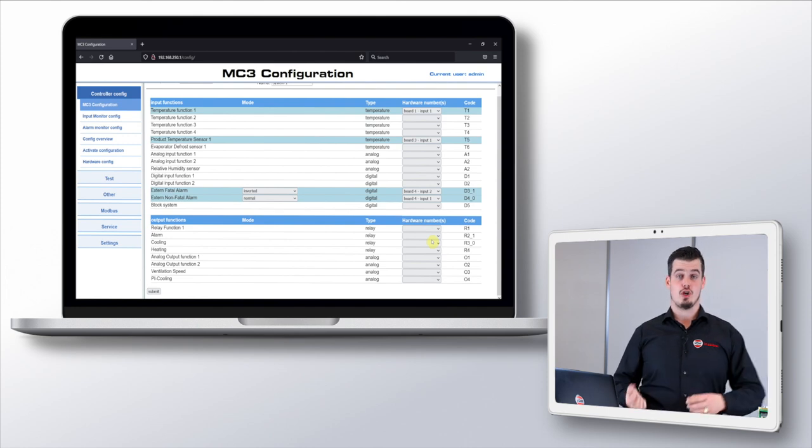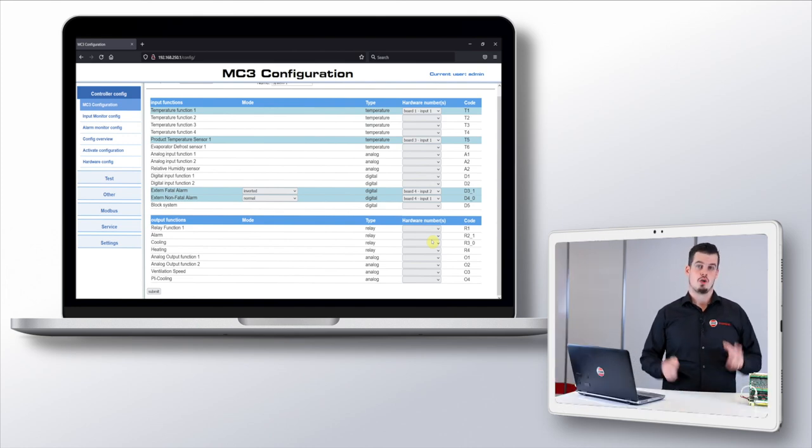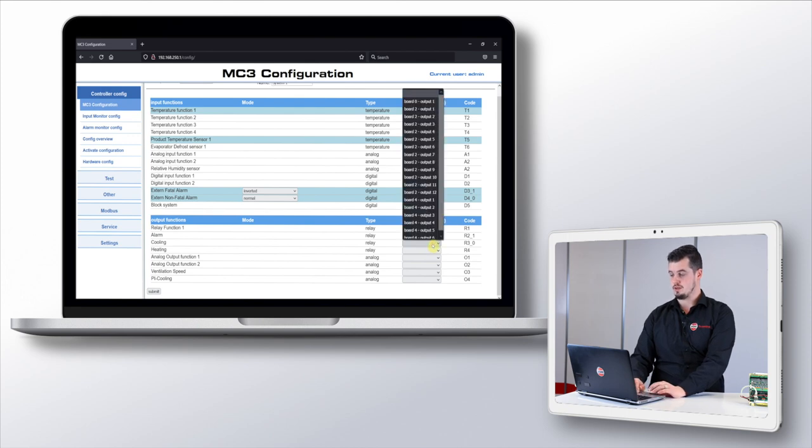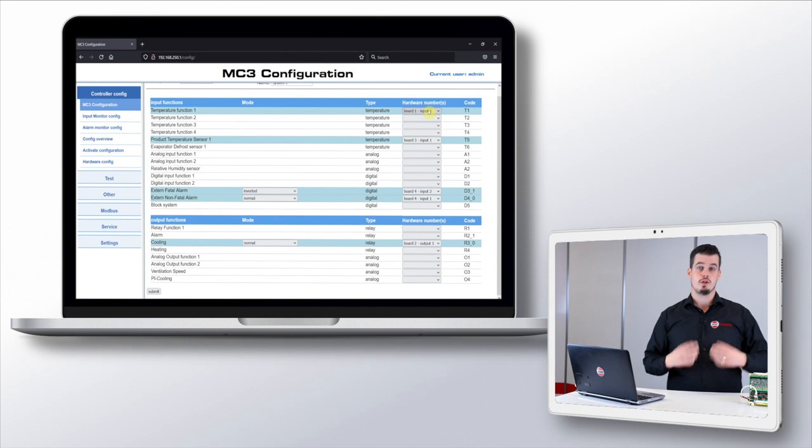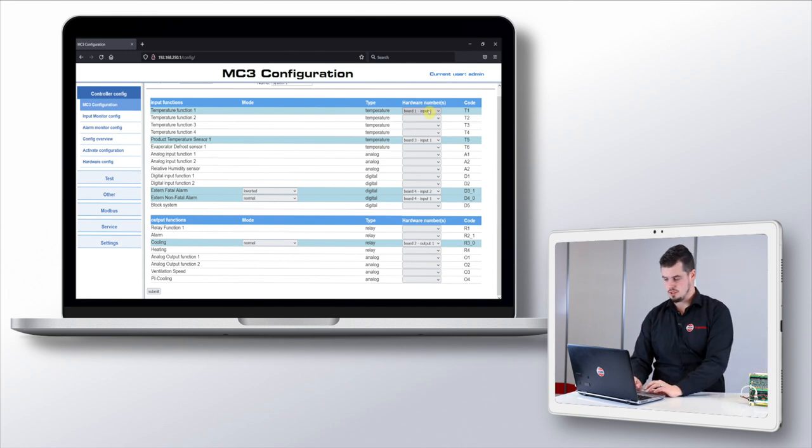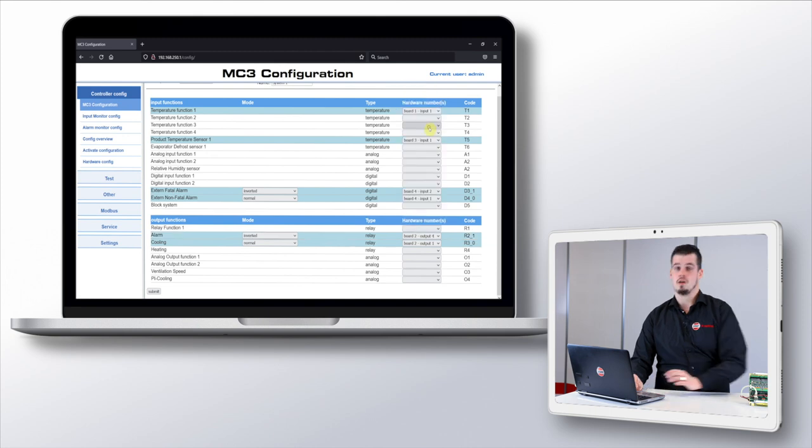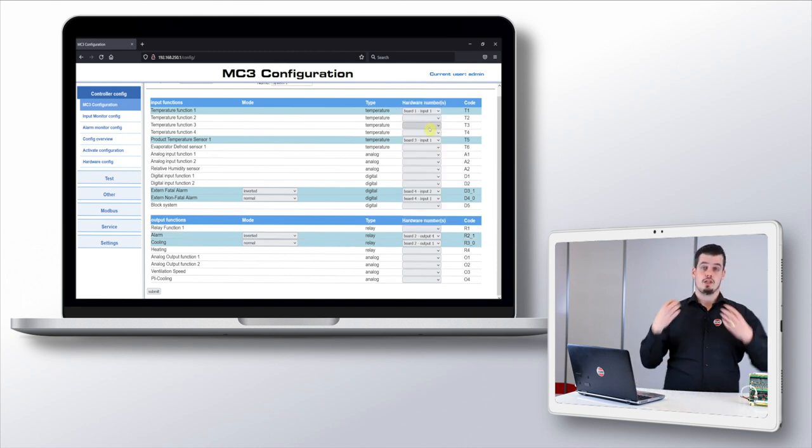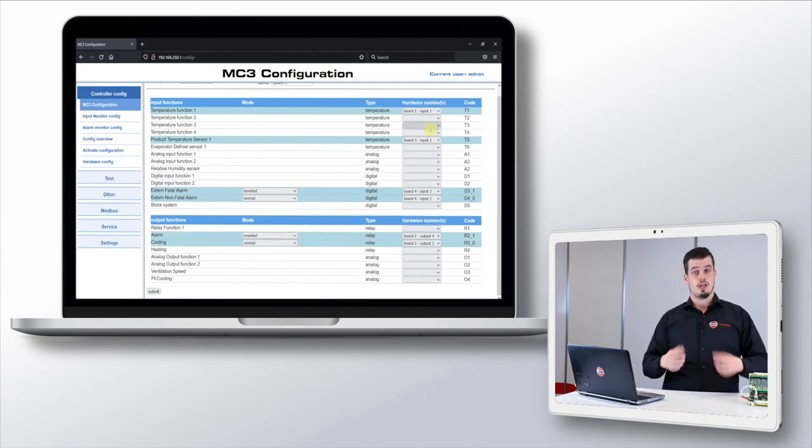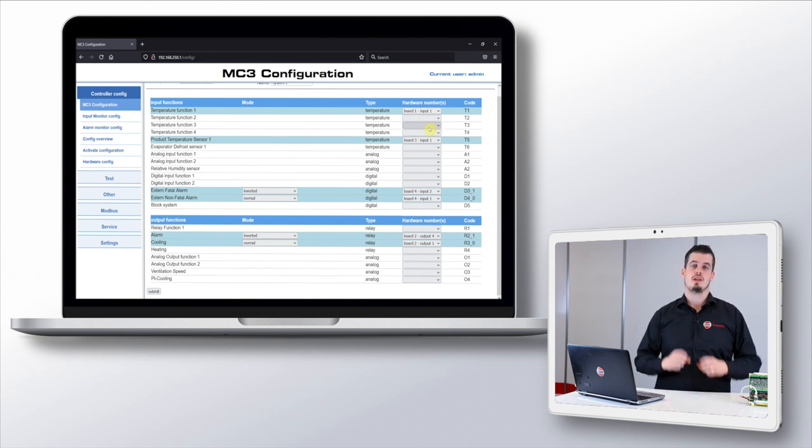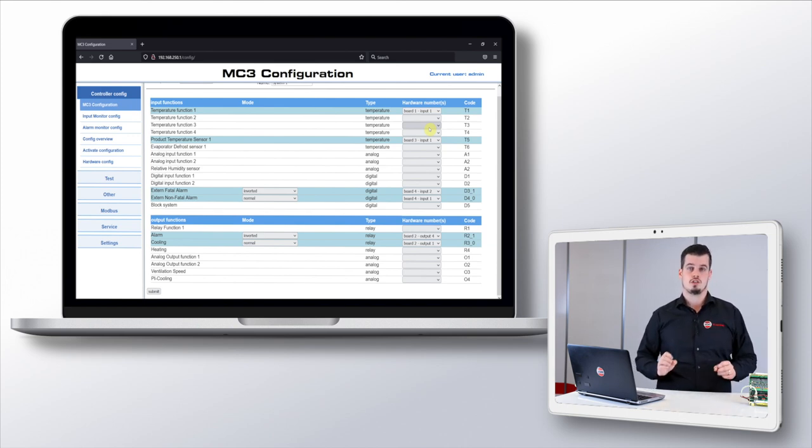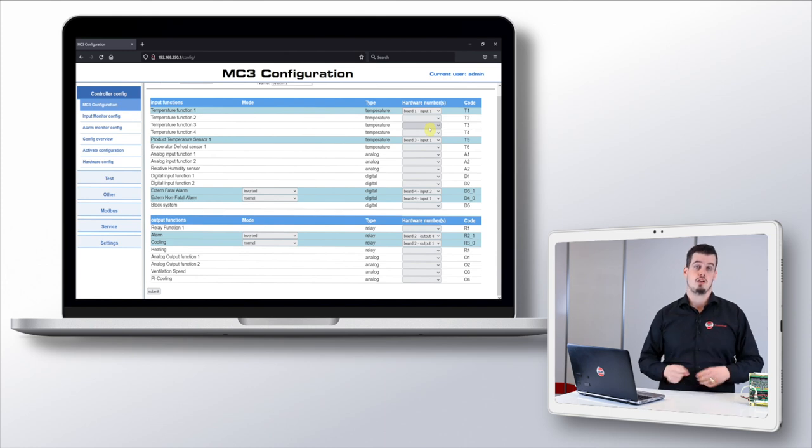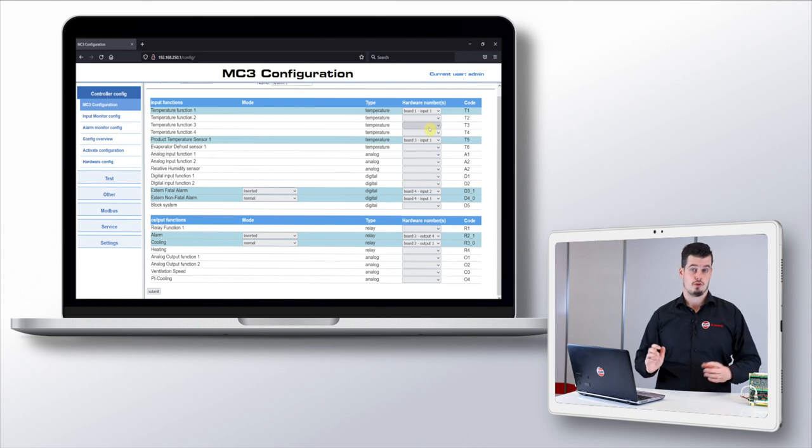So let me show you how we can configure this. We navigate to our function, cooling output, and select board 2 output 1 from the dropdown menu. We do the same for our alarm output and select board 2 output 4. You might already noticed but also for the relay outputs we can select the normal and the inverted option. Since we want to have a failsafe alarm contact which breaks the connection if there is an alarm, we'll use the inverted option for the alarm function.